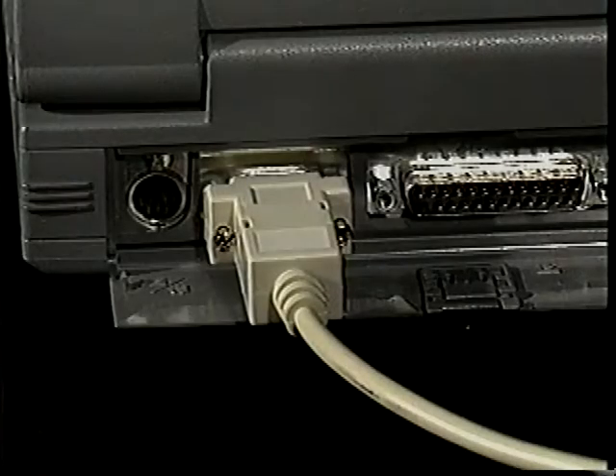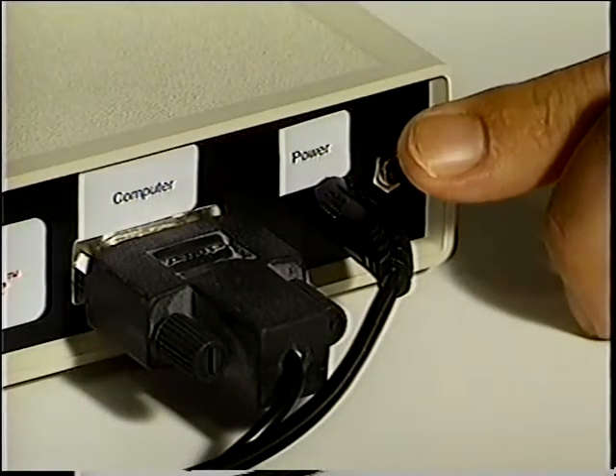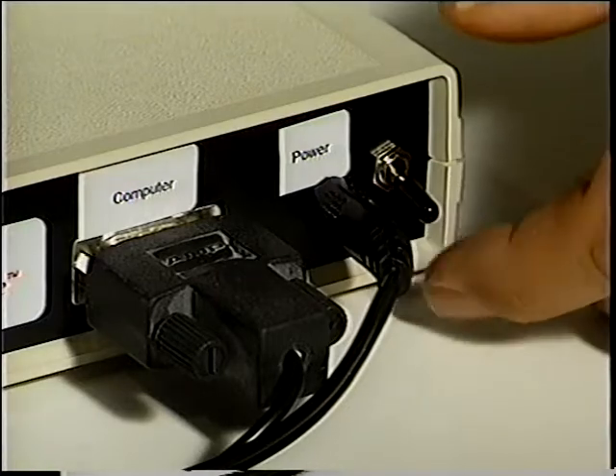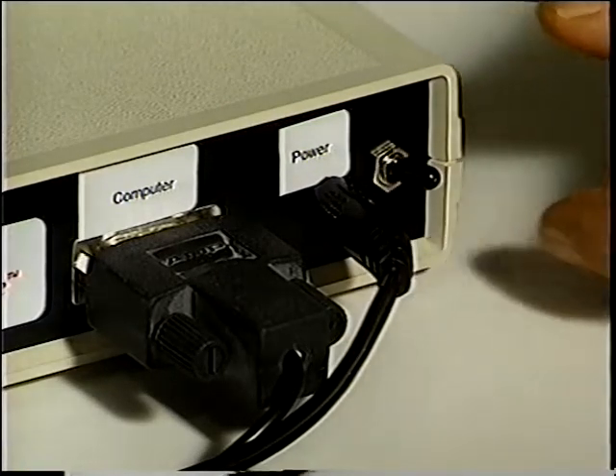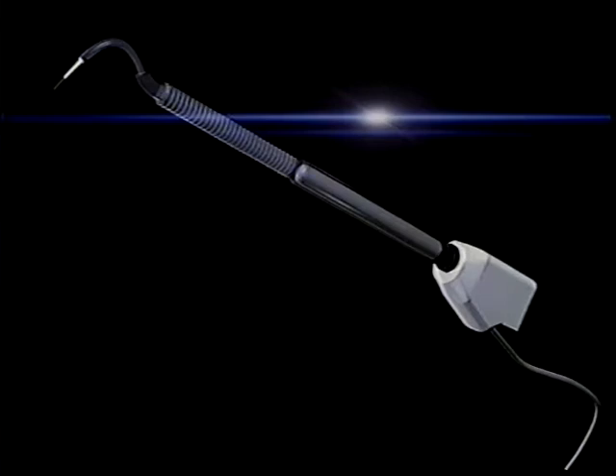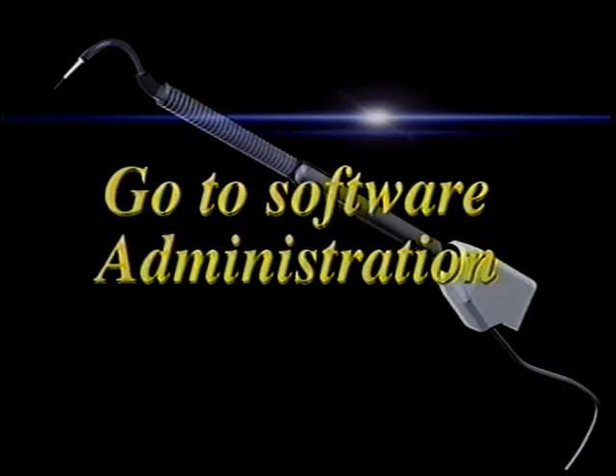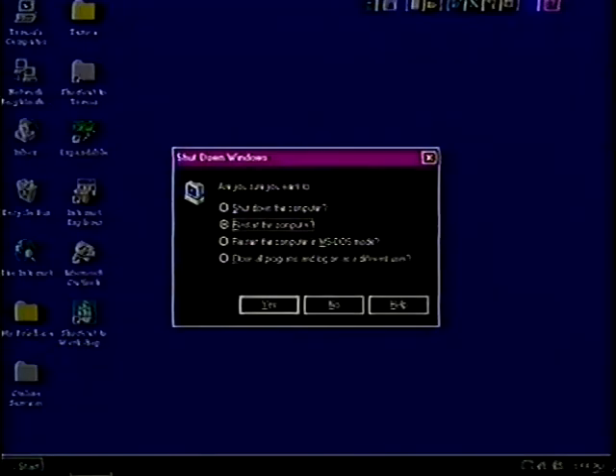If the green light remains on, it usually means that the data is being sent, but for some reason is not being accepted by the computer. This usually indicates that the information is being sent from the probe to the wrong COM port. If this happens, turn the switch off and then on again to clear the interface unit. Go back to your computer's software administration and select a different COM port. If you make a change in the administration setup, you must reboot your computer.